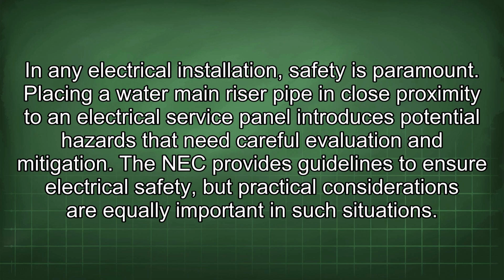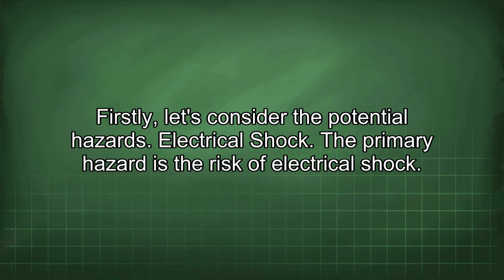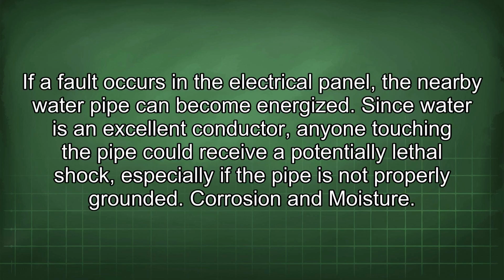The NEC provides guidelines to ensure electrical safety, but practical considerations are equally important in such situations. Firstly, let's consider the potential hazards. Electrical shock. The primary hazard is the risk of electrical shock. If a fault occurs in the electrical panel, the nearby water pipe can become energized. Since water is an excellent conductor, anyone touching the pipe could receive a potentially lethal shock, especially if the pipe is not properly grounded.